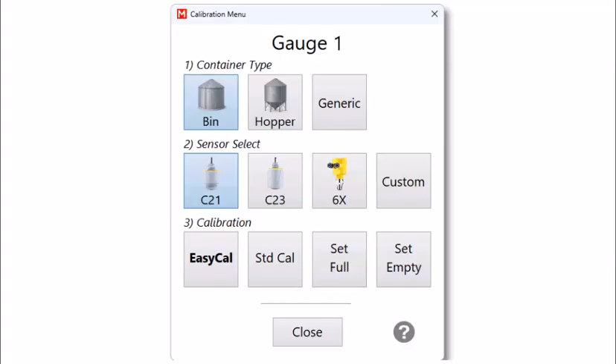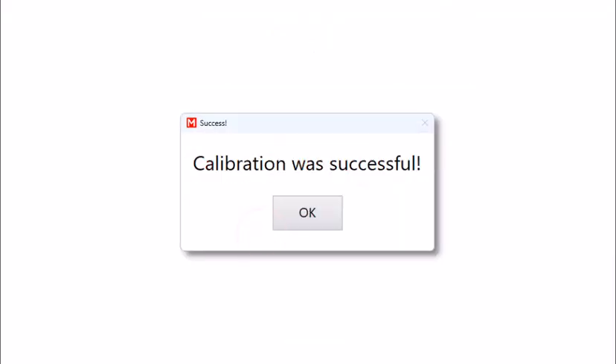You can choose to top off the bin to fill the extra space if your contents have coned, but we do not recommend using the Set Full button after doing so. Changing the bin's full level after topping off with wet materials that have coned can cause bin overflow if drier contents are in the bin next year. With that being said, to use your Set Full or Set Empty functions, simply press the button and acknowledge the pop-up. Your bin's 100% full or 0% empty levels will be automatically changed to the current distance detected by the sensor.